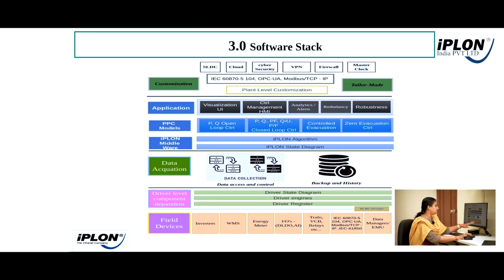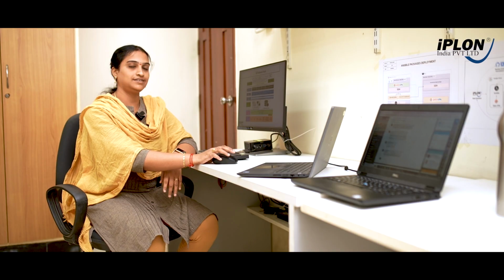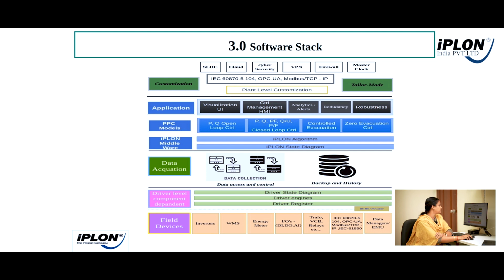When it comes to the software stack, the first layer will be the field devices. In the sense, the field devices are like inverters, weather stations, energy meters, and all. Once data is collected from the field devices, it is parked inside the hardware. From this hardware, we have to send this data to the databases. So here InfluxDB and Postgres are the databases that we are using. All the real-time data will be stored in the InfluxDB, and the alerts and alarms will be saved into Postgres, and also the logging commands which were given by the operator will be sent to the Postgres database.